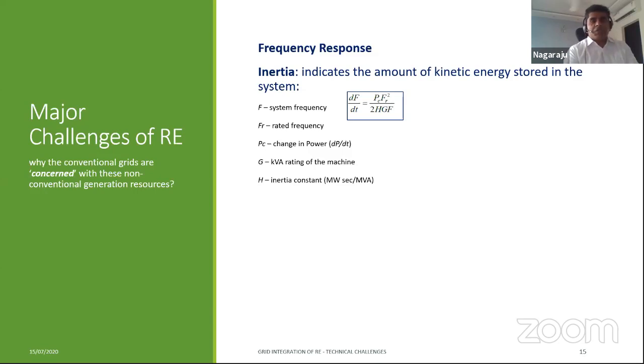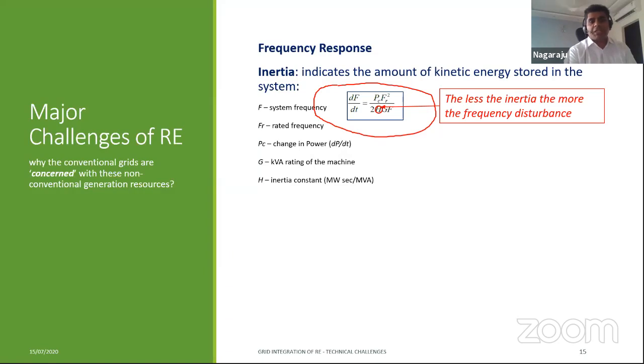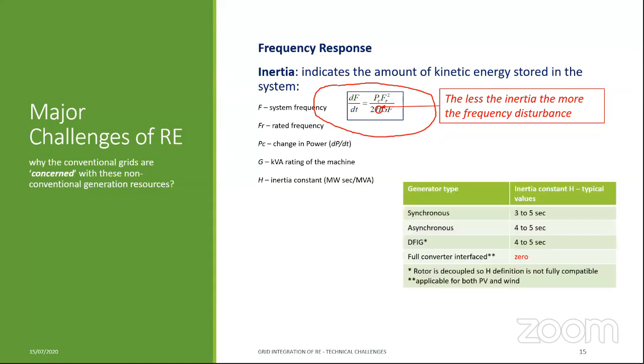So in terms of the fundamental equation, you see this equation here, it shows the rate of change of frequency as a function of various parameters. And one important parameter is the time constant H, which is the inertia constant. The more the inertia constant, the less the frequency change. That is the inertial response. So what are the inertia constants of various machines? Synchronous machines, we usually say 3 to 5 seconds. And asynchronous machines like induction motors, we have 4 to 5 seconds. Then doubly fed machines, which are induction generators, again 4 to 5. But as I said, the definition of time constant here is not strictly applicable because the rotor is kind of disconnected from the AC system, right? Then the full converter interface to renewable energy, which has a front-end power converter, has zero inertia.